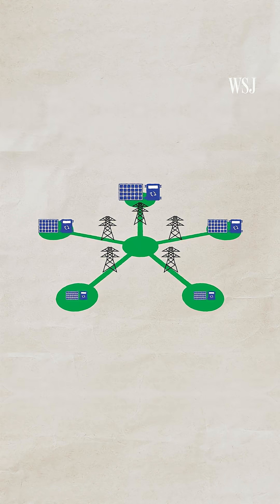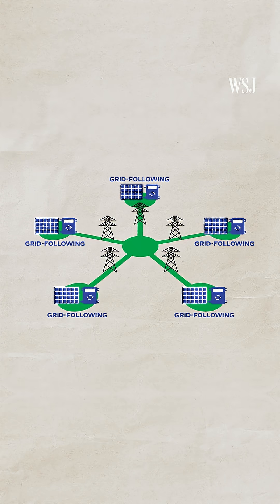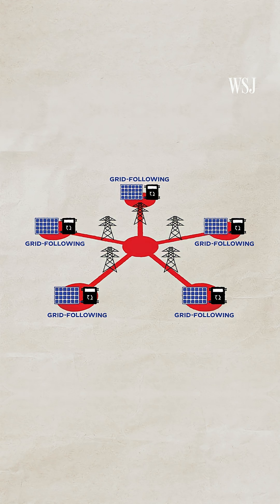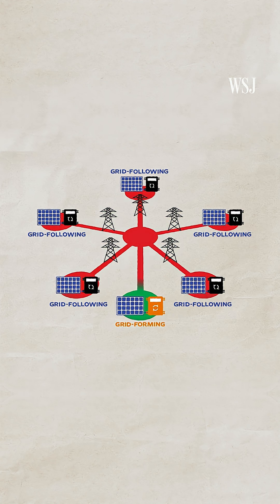Most inverters at renewable power plants today are grid following, meaning they rely on the grid's voltage and frequency. So if there's an outage, the inverter loses its reference and can't function. Grid forming inverters are more advanced. They can operate independently and support the grid when there's a disruption.